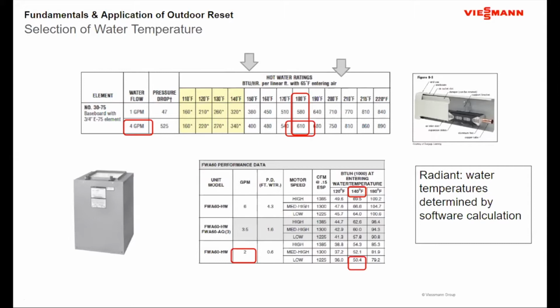You know, a little side note over here, if I'm doing radiant, typically from a radiant standpoint, the water temperature is going to be determined by the application and a software package to design it. So in radiant, we say this is how we're going to design it. The program tells you what the water temperature needs to be. But from an aspect of outdoor reset and heating the building, through one of these methodologies, we will then pick a water temperature so that my system can be balanced.